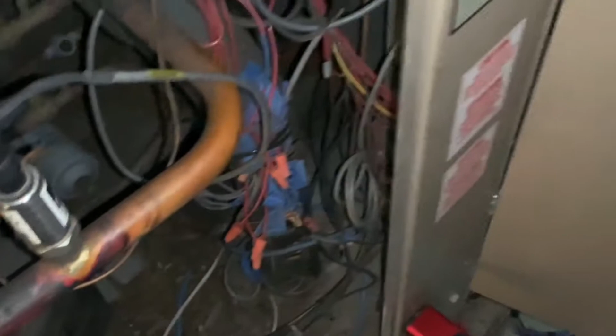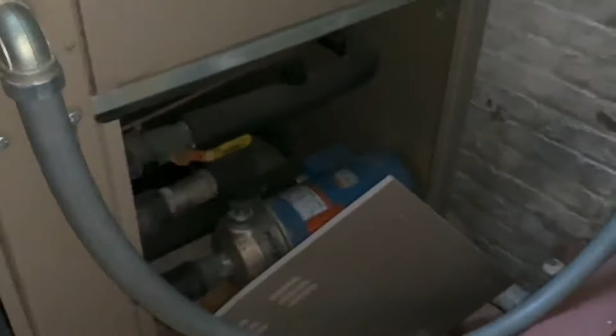Let's look at this chiller here now. Also, the headmaster, in order to control the head pressure, not only blocks off the condenser and bypasses the condenser, but coupled with that, there's usually a fan cycling device that controls the condenser fan based on pressure. So if the pressure is up, the fan will spin, rejecting some heat, and if the pressure is low, it will stay off.